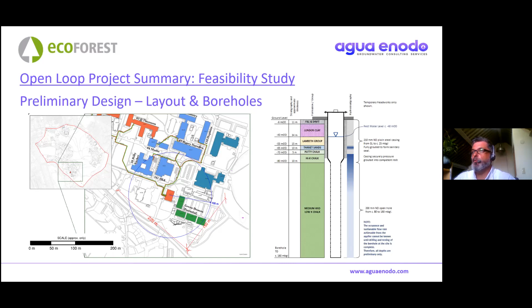At the feasibility stage, we should have a fair understanding of what loads we can service based on the number of boreholes we think we can fit in, the available delta T, and the abstraction and injection temperatures - which might be set in collaboration with the heat pump designer or according to regulatory constraints.